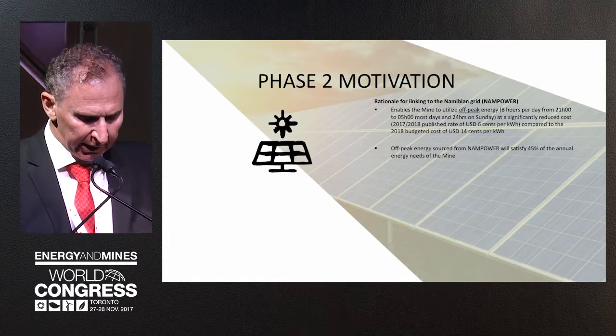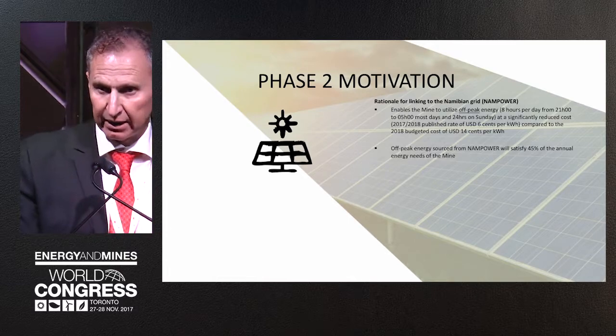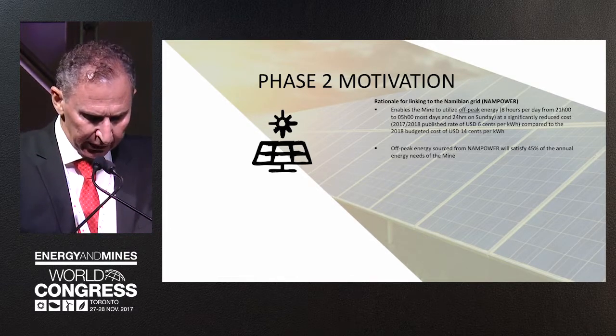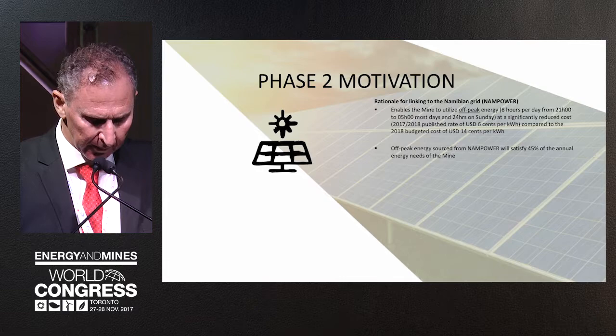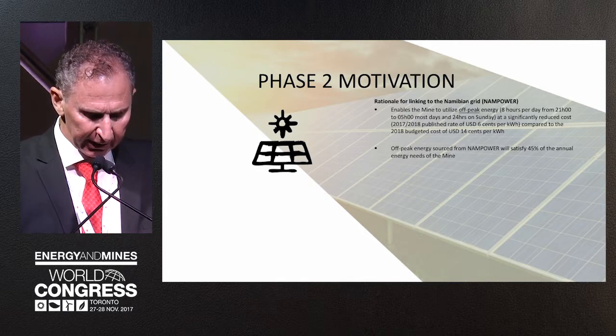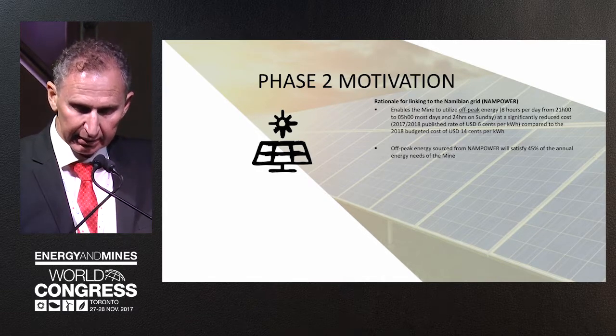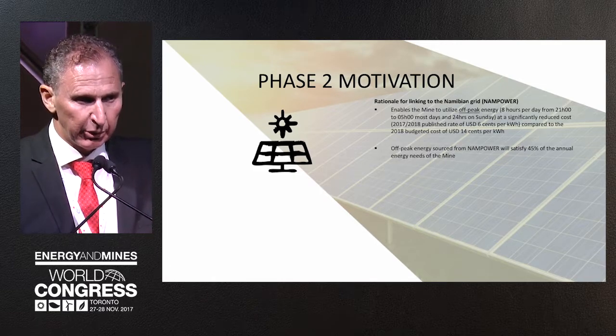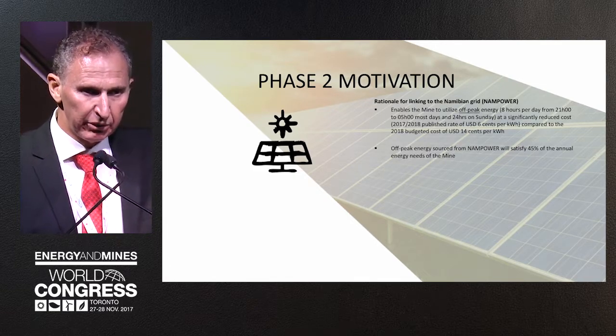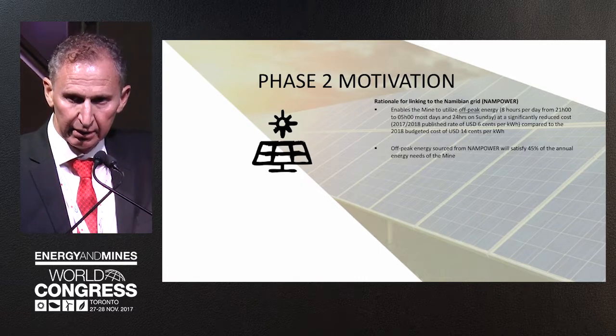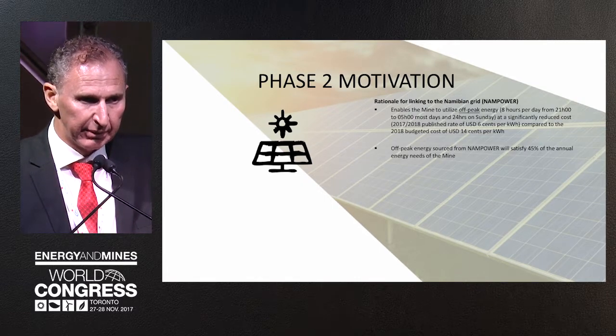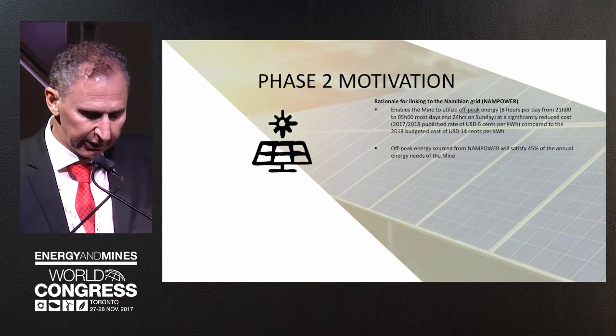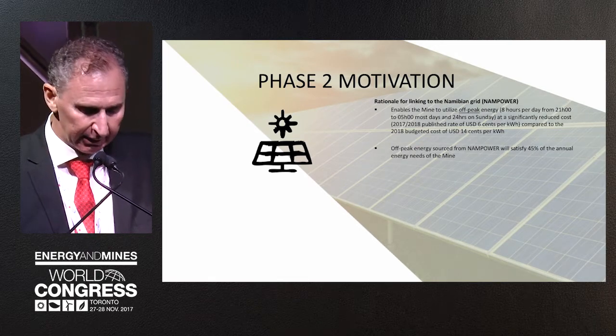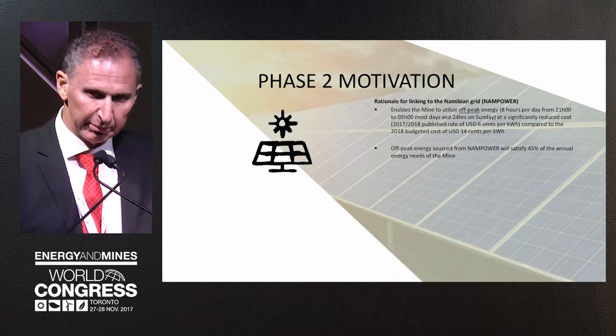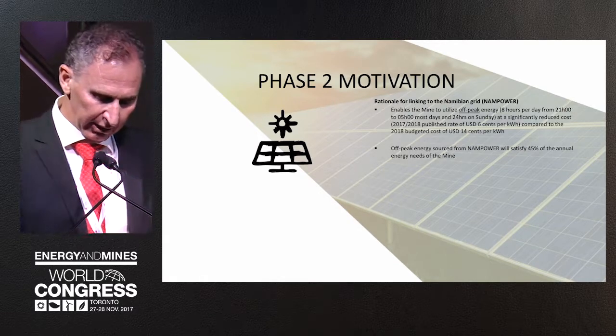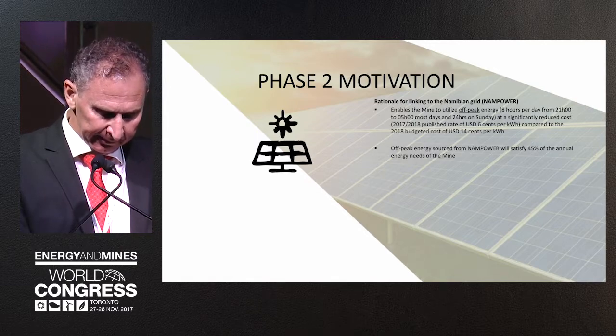The off-peak energy source from NamPower will satisfy 45% of our demand, which is a lot, as you can imagine. It's going to reduce engine operating hours and reduce maintenance intervals, obviously. I need to point out that all the savings I've been speaking about are purely through fuel savings alone, not through any reduced maintenance interventions, which is a lot of money, millions of US dollars. So we looked at the most conservative model to justify this plant and the grid link.